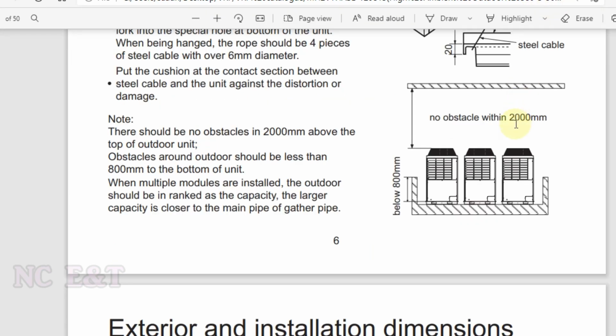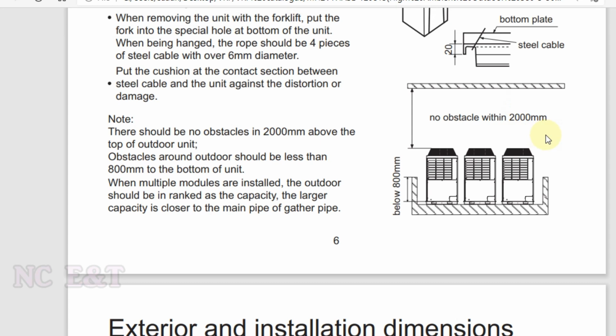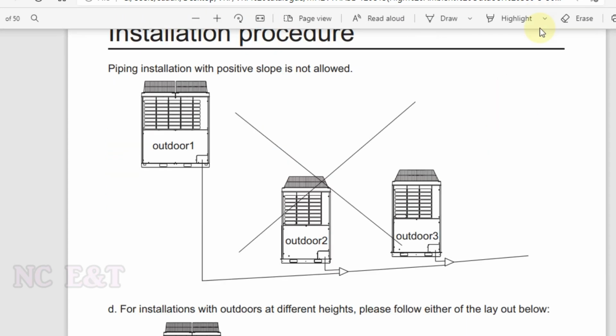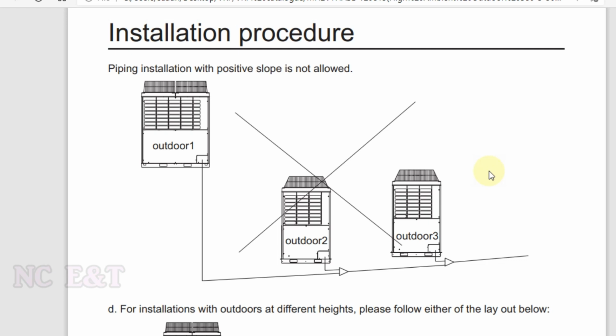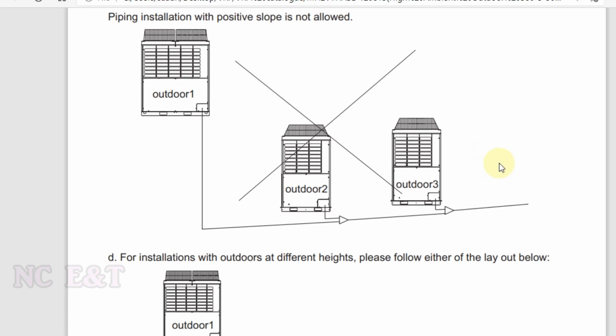If we have a shade or slab above the outdoor unit, there must be a clearance of minimum 2 meter between the slab and the top of the outdoor units. For the refrigerant piping network, we must try to make it horizontal, and if we are making it in slope, the slope must be towards the indoor unit.